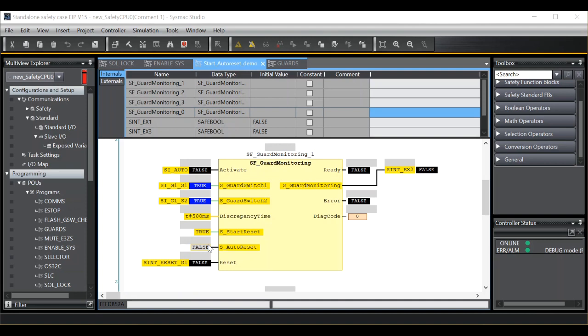In this case I would expect upon activation of the function block, providing the guard switch conditions are true, the output will move to a true status. However, then on transition of the guard switch from true to false and back to true, a manual reset will be required.